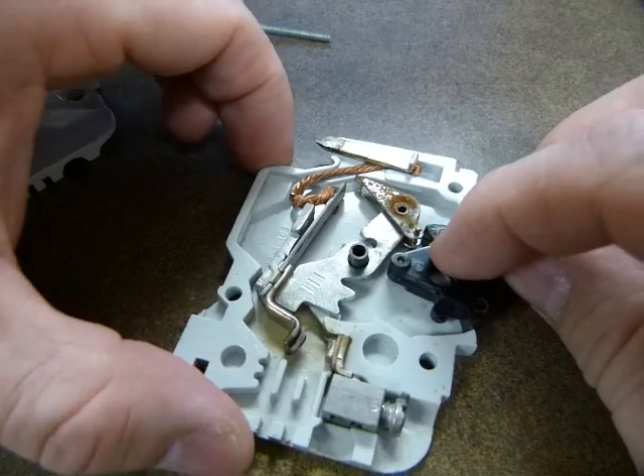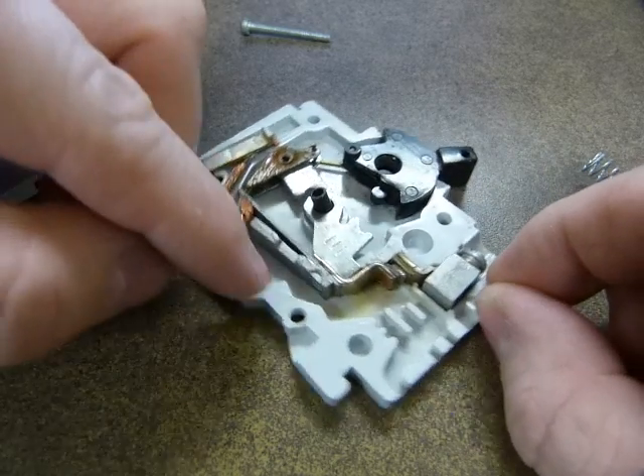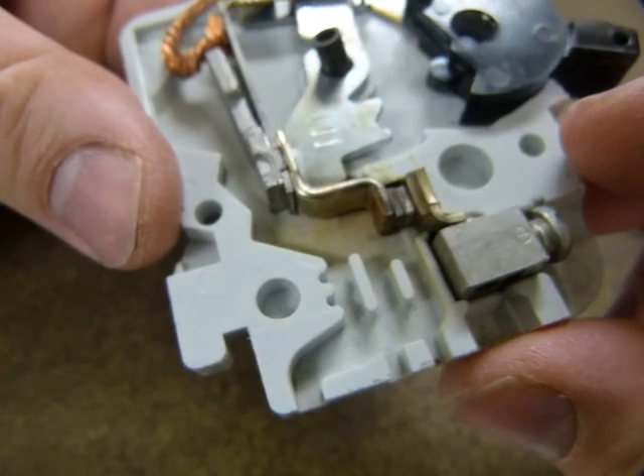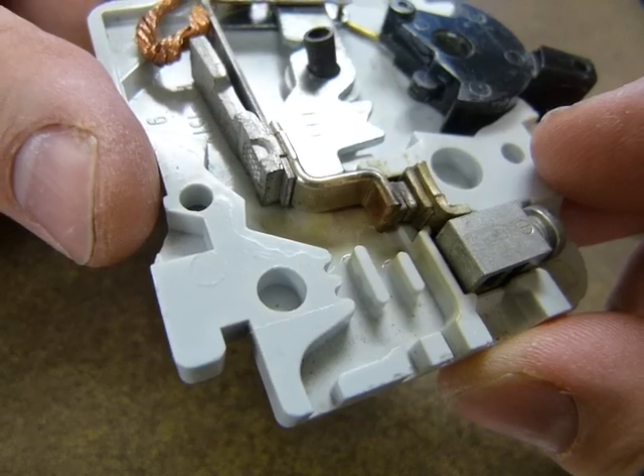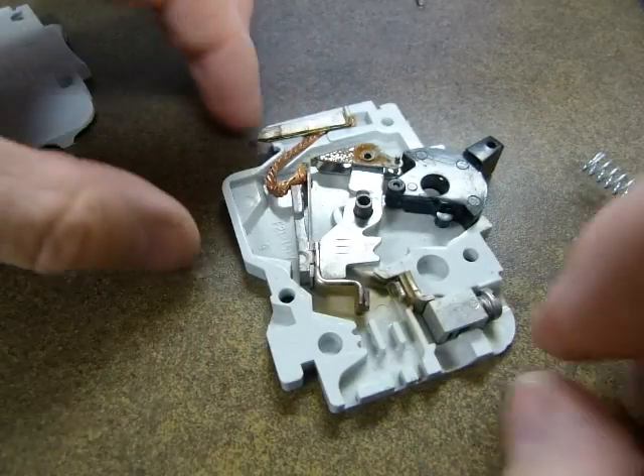That's how it resets and opens or closes. When too many electrons try to rush through this component — this copper-aluminum sandwich here at the top — it heats up. Copper and aluminum are dissimilar metals, so they expand at different rates. As they expand and pry themselves apart, they snap and open the circuit.